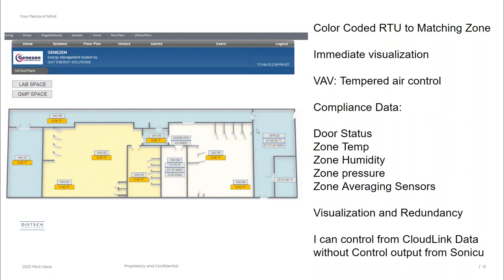On the right-hand side of the floor plan, you can see here where we had just a standard office VAV with one temperature. In this particular case, they built out an office within there, and they wanted to monitor both. Rather than going back to pipe and wire and trying to get everything bridged into the BMS, you can launch the additional sensors from Sonicu. Now we're seeing 2 different zone temps as well as room humidity, and by bringing that back into the BMS, I can control that VAV off an averaging temp.